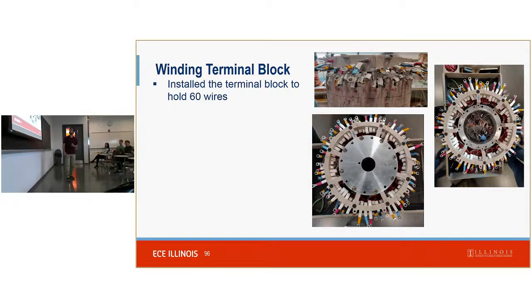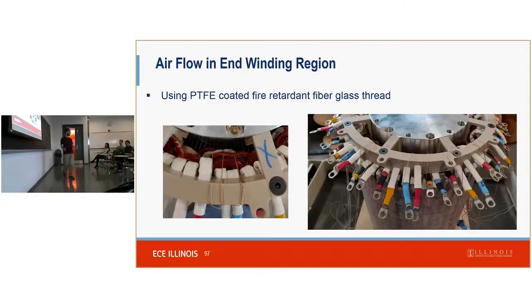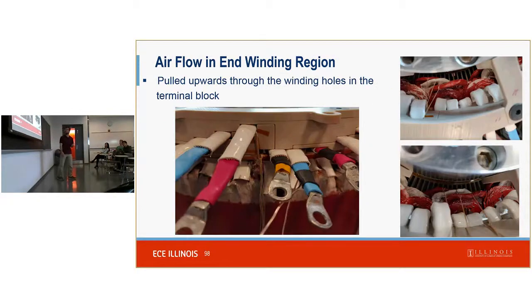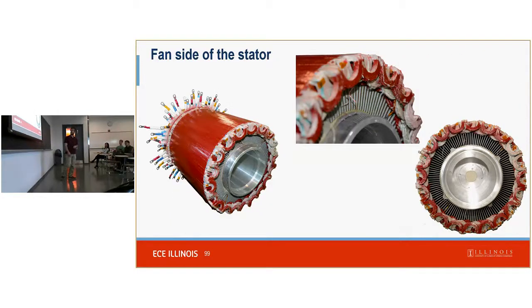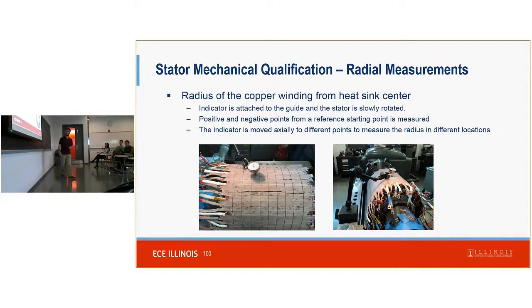And so built and installed that, and that provides quite a bit more order and consistency with where those are. And then to mitigate blocking the airflow on the inlet side, a fairly simple solution was to tie string onto the parts that were blocking it the most and pull those up and open up a little bit more flow. Not a perfect solution, but it was the solution available to us. Close up of that. And so this is the fan side of the stator. So this is the outlet side.